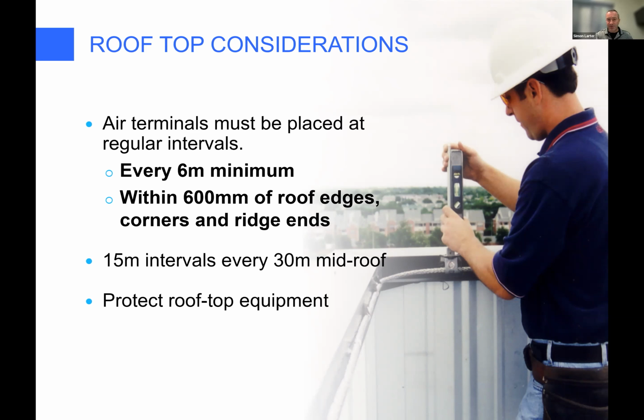When you distribute them around the edges and corners, along the flats you want that lightning rod to be distributed every 6 meters minimum. You can put taller rods, say 600 millimeter tall rods instead of 300 millimeter.